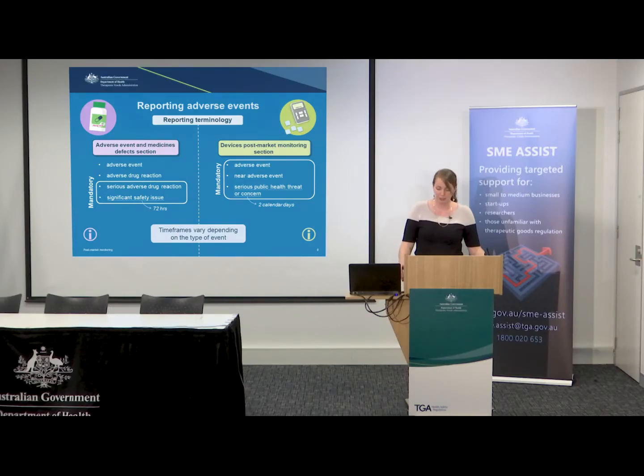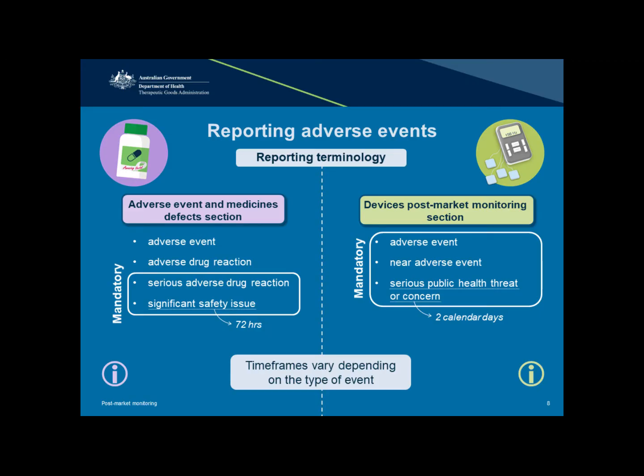Now, let's look at medical device terminology. These have 3 main categories. An adverse event for medical devices is an event that led to death, a serious injury, or serious deterioration to a patient, user, or other person. A near adverse event is an event that might have led to death or a serious injury. A serious public health threat or concern is a hazardous event arising from systematic failure of a device, usually coming from an adverse event or near adverse event itself. Typically, it would be something that the TGA must act on swiftly to avoid impact on the public, as opposed to an individual's safety. For medical devices, all of these are mandatory for you to report to the TGA.